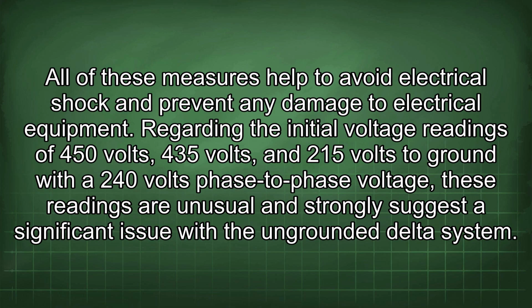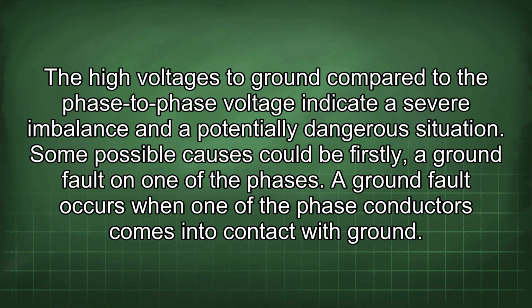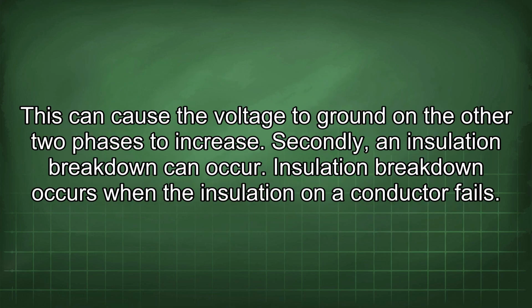Regarding the initial voltage readings of 450 volts, 435 volts, and 215 volts to ground with the 240 volts phase-to-phase voltage, these readings are unusual and strongly suggest a significant issue with the ungrounded delta system. The high voltages to ground compared to the phase-to-phase voltage indicate a severe imbalance and a potentially dangerous situation. Some possible causes could be, firstly, a ground fault on one of the phases. A ground fault occurs when one of the phase conductors comes into contact with ground. This can cause the voltage to ground on the other two phases to increase.